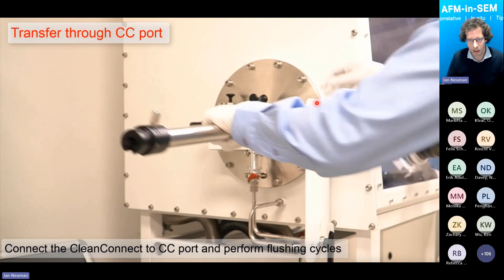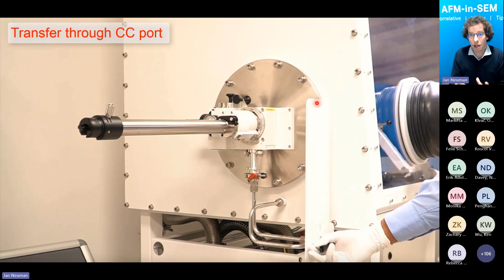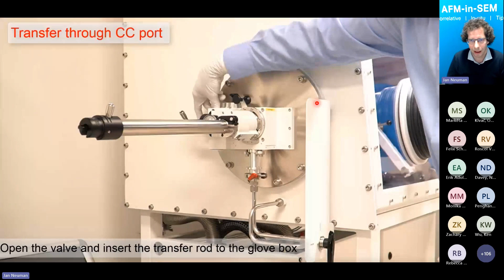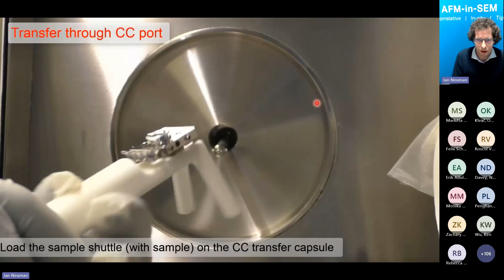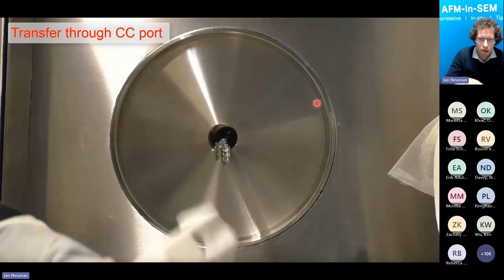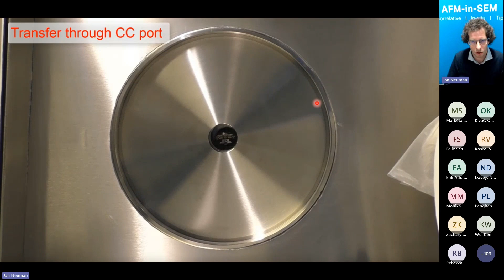So you have a glove box. On the side, you can open the port. You mount there the Clean Connect transfer chamber, which enables you to transfer the sample without any air exposure. It's quite straightforward. You just move in the sample holder, mount the sample holder to the rod, put it into the transfer chamber in the Clean Connect, close it, and evacuate the transfer chamber.